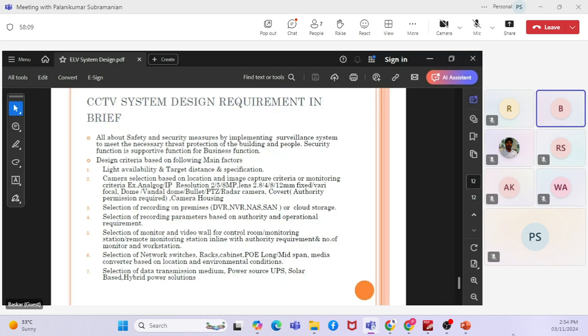Apart from that, the power source should also be taken care of, whether it's inside the building or outside. If an existing power source is there, then you can take the electrical raw power and dedicate the UPS. You need to choose the UPS based on the number of switches, either 1 kVA, 2 kVA, 3 kVA, 6 kVA, or 10 kVA, or a control room may require 10 kVA or more. So you have to choose the UPS based on the load conditions. Proposing the UPS is mostly a part of the CCTV system itself. Choosing a higher kVA rating of the UPS will also impact our design cost, and so will the other types of power sourcing method.